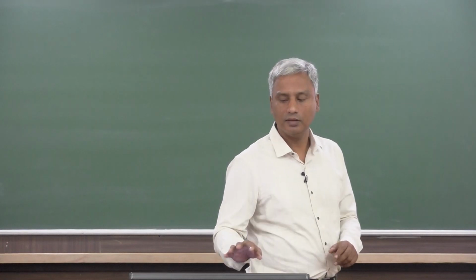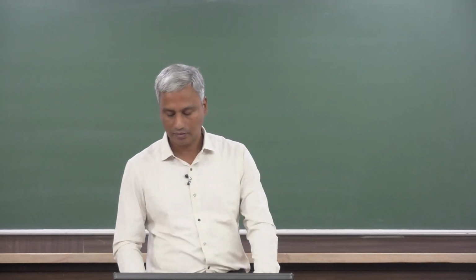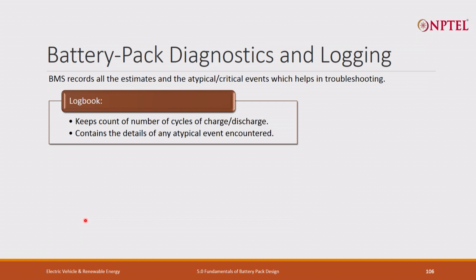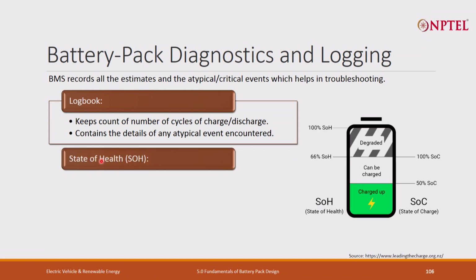Such conditions are written into the logbook function. It also keeps measuring the number of charge or discharge cycles for warranty as well as life, to know the life of the battery pack. This is also important for SOH calculation. Any atypical event, like an external short circuit, also gets written back into the logbook, apart from the regular parameters of interest.